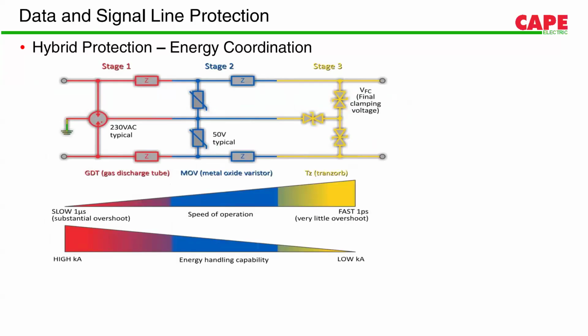And normal SPDs have three-stage protection: stage 1, stage 2, and stage 3. In stage 1 we protect through a GDT, in stage 2 through a metal oxide varistor, whereas in stage 3 we provide diodes. Stage 3 diodes are the fastest operating devices, whereas stage 2 MOVs have somewhat lesser operating speed but higher energy handling capacity, while diodes have the lowest voltage protection level but also the lowest energy handling capacity.